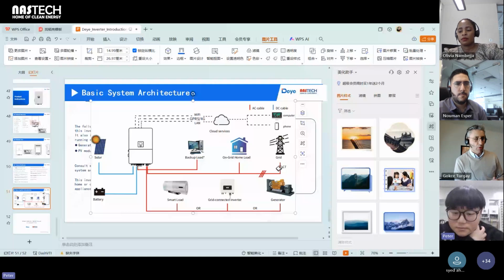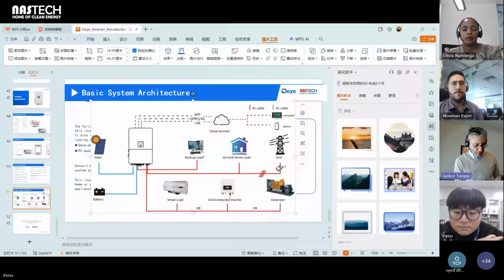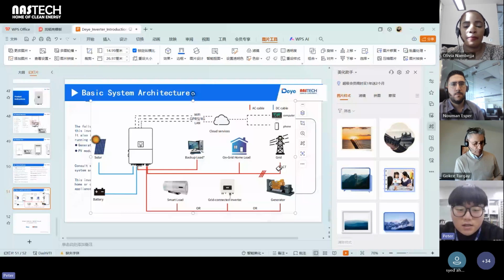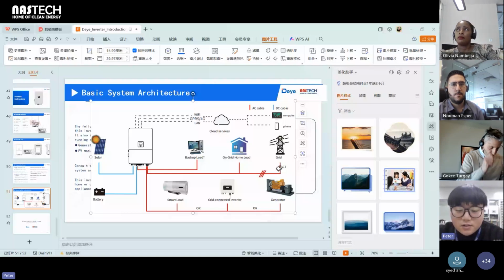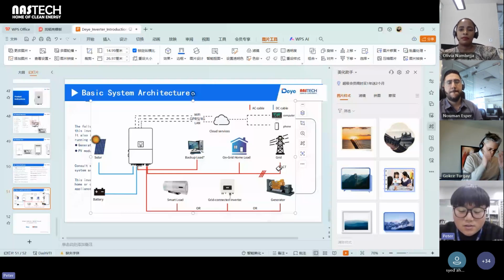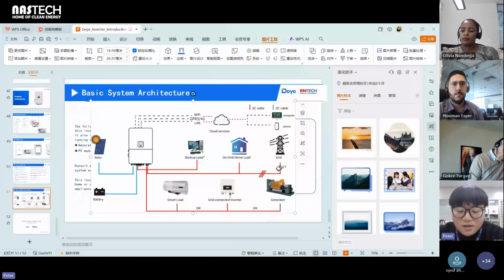Yes, correct. Okay, so the meters, we already know, are the 3-phase meters that they approved, we will use them. For the ATS, can we get the specification maybe later on? Is there any decided brand and capacity that we can suggest to our customers? Actually, we don't have a recommended brand, and the capacity depends on the generator size and also the system size. But there is one function that the ATS should have. Once it transfers from the grid side to the generator side, it should have a dry contact output to start the generator. In that case, the generator can be automatically started without manual operation.